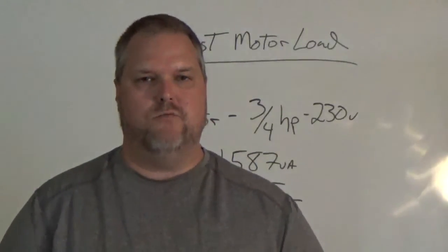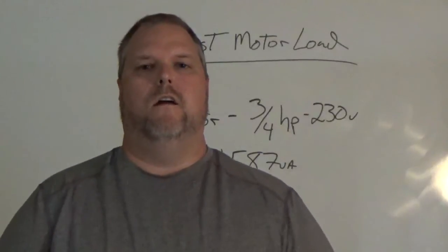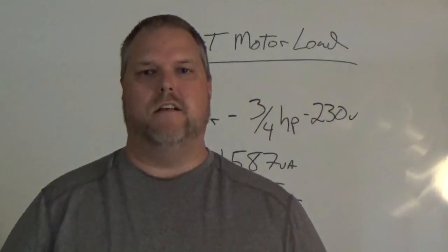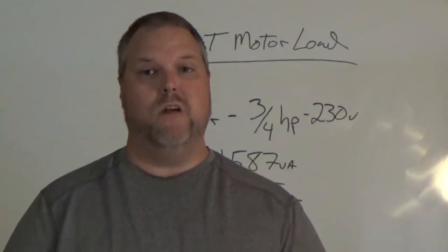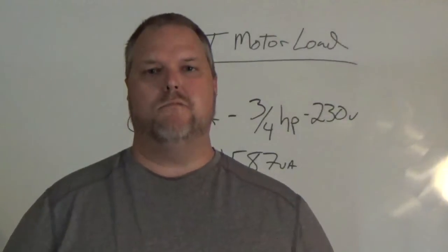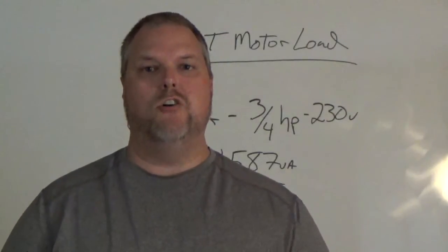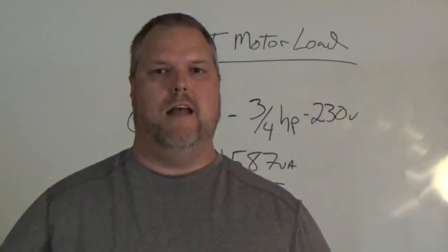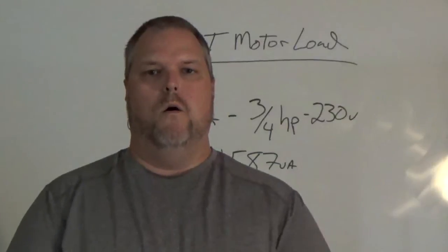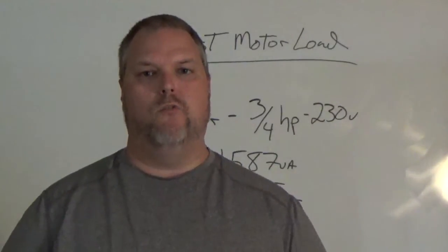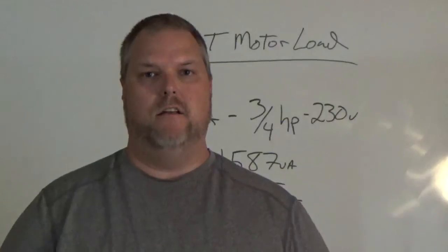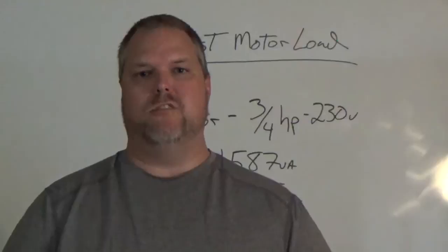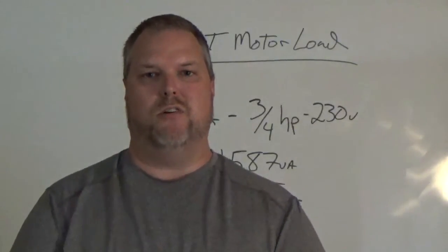So my question is: why 0.25? Here's what we have to figure. Going through motors, Article 430 is going to tell us that if we are adding multiple motors, which we have in a dwelling, the largest motor needs to be calculated at 125 percent and every motor after that needs to be taken at 100 percent. When we did the fixed appliances, we already took it at 100 percent. So one of those motors we need to just multiply by .25 to give us our largest motor calculation.